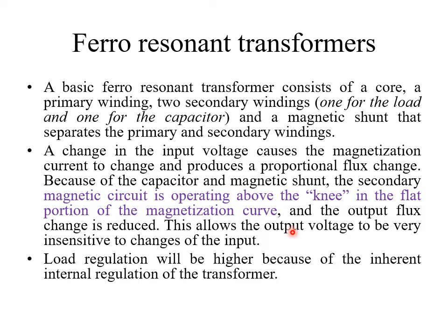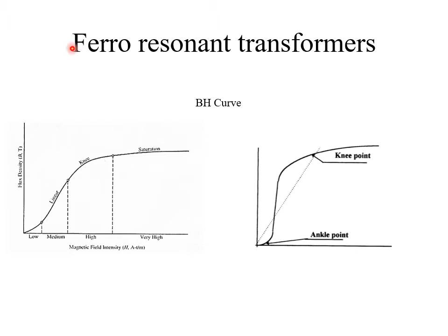The secondary magnetic circuit is operating above the knee point, and the output flux change is reduced. This allows the output voltage to be very insensitive to the changes in input. So whatever the changes in input, it will not affect the output because of the capacitor and the magnetic shunt. All right, and this is the knee point in the BH curve, which we were speaking of before.